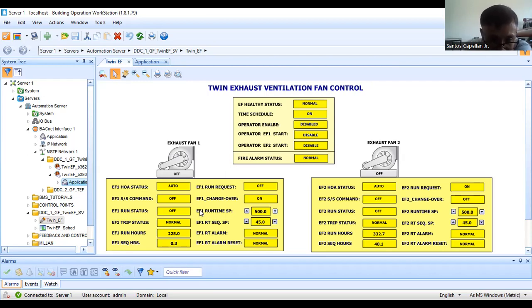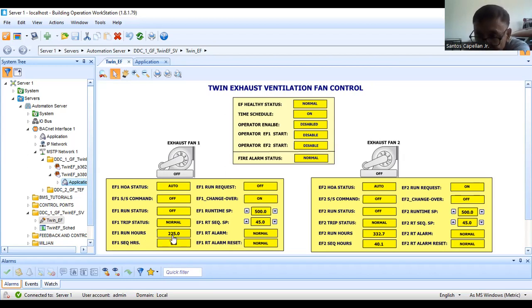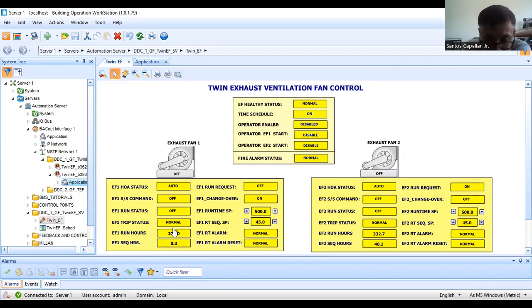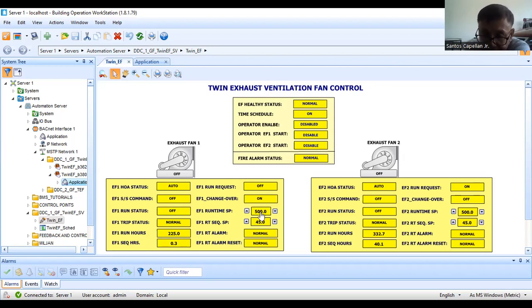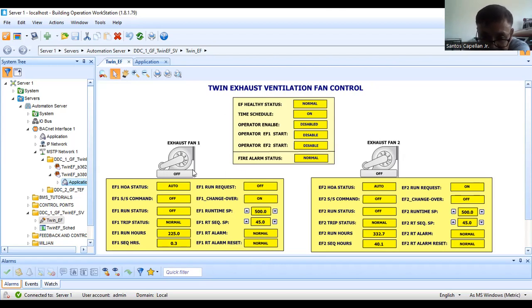I have here the EF run hours. This is the accumulated EF run hours. As you can see, this fan is belt driven. For maintenance purposes, we need to prompt the maintenance people. I have here the run time set point. If this fan runs already 500 hours, then this EF run time alarm will be on.